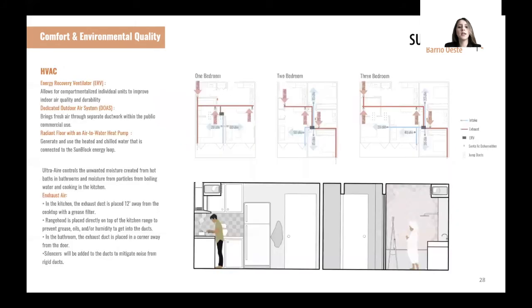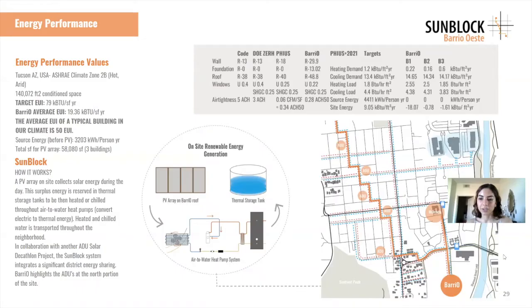Lastly, the units have an internally balanced ventilation that allows for compartmentalized individual units to improve indoor air quality and durability. An ultra air dehumidifier controls the humidity and keeps the interior air above the dew point. Due to the use of radiant cooling, it is critical to keep the interior floors above the dew point temperature to avoid condensation. The EUI target for the mixed-use multifamily division is 79 kBTUs per square foot per year.